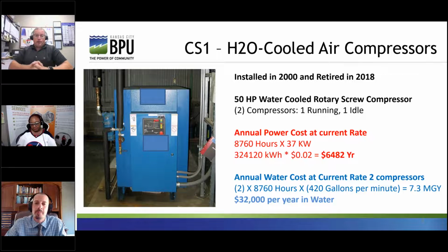It's case study 1. We had 2 compressors installed in 2000 when the plant went online, and they were retired in 2018. They were 50 horse water-cooled rotary screw compressors. And there's a lot of processes that rely on compressed air at the plant, mainly filter and pump valve actuation.